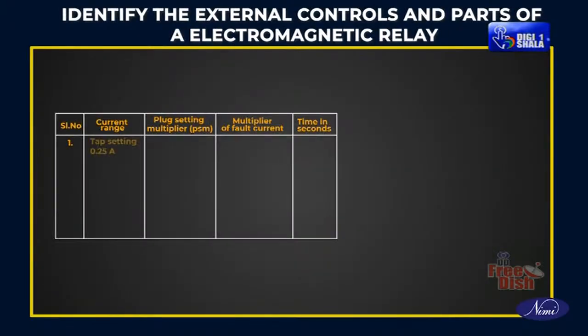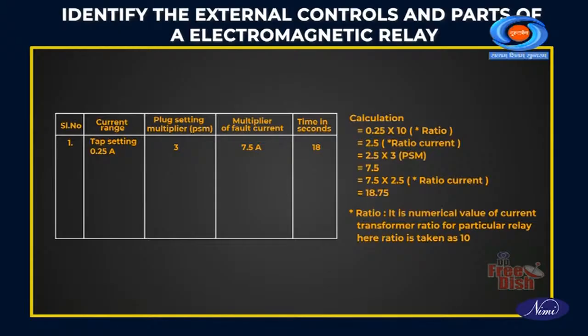When the tap setting is set at 0.25 amperes and PSM is set at 3, the multiplier of fault current is 7.5 amperes and the time in seconds is 18. Will it trip? See the calculation. Similarly, when the PSM is 4, the fault current is 10 amperes and the time in seconds is 10.5. Will it trip? Similarly, when the PSM is set at 6, the multiplier of fault current is 15 amperes and the time in seconds is 8.5.